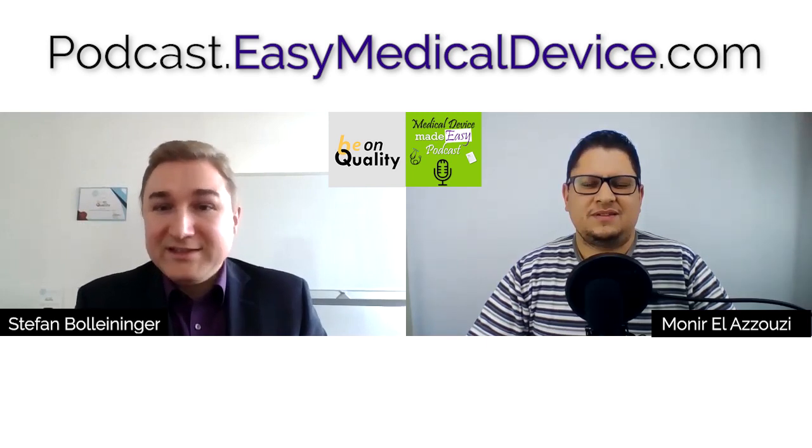And very important on that step, if you have found your gap or no gap at all, then you need to make contact with your certification institute who can give you the ISO 13485 certificate. In that step, you will need to start with their offer, make the commercial proposals, and have all the discussions: how many people you are, the setup of the company, how it will be structured. That's sometimes a very hard thing to get completely done with them in a fast time. And then you will first need to pay.